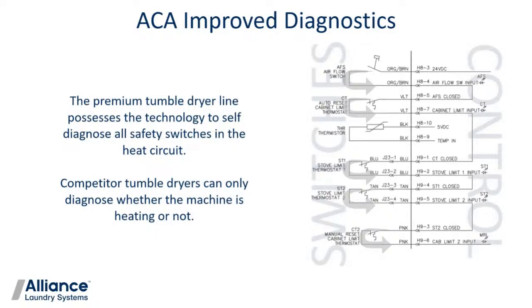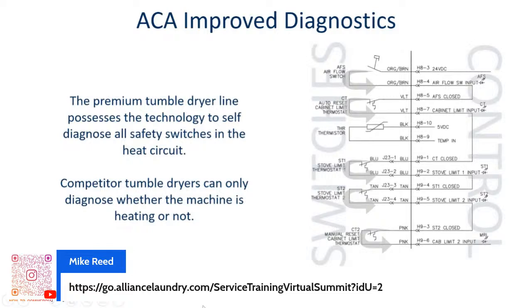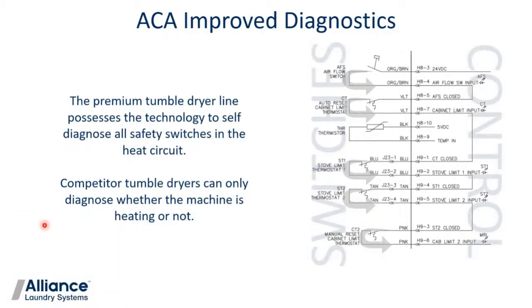When we look at the heat circuit, there's a bunch of safety switches that have to be intact before we can ever operate the heat. So the way things go here is when the machine calls for heat, so to speak, to start this heat circuit, we send signal out through the airflow switch, and then that signal comes back directly into the control. If we follow that signal, it goes out to the auto reset cabinet limit thermostat, and then it comes back in. So the fact that each switch has a wire in, wire out tells us that the control can monitor each one of these switches individually.